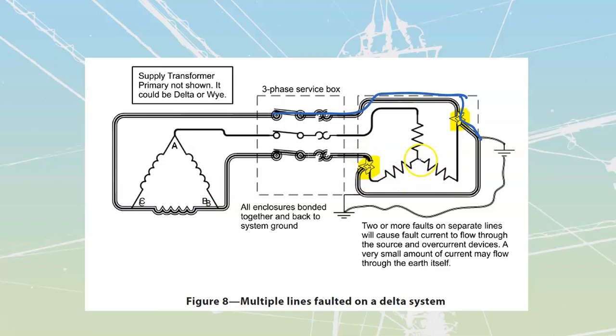It can go all the way in here and then split, sending some back onto the A and the B. Or alternatively, it's got the option to travel through the bonded system and make contact with the other grounded down line. As soon as it does that, it's going to make contact with my B line, and we see we'll have overall a complete path for current going through here.